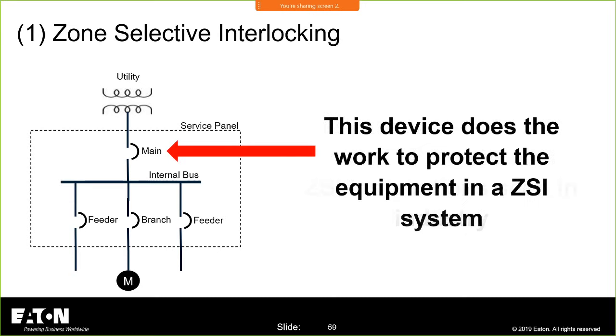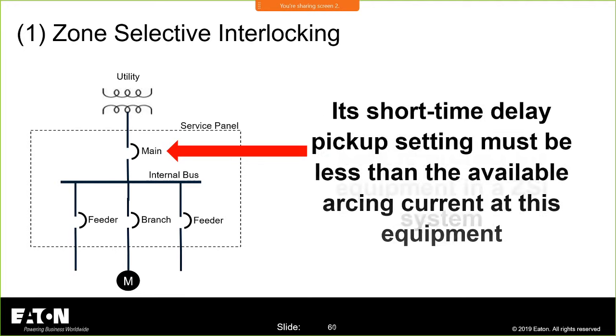because it doesn't get you selective coordination. In a ZSI system, that main device is what does the action to clear the fault. And it actuates on its short time delay pickup setting. So what you're going to have to do to meet this code is ensure the short time delay pickup setting is less than the arcing current. You're going to have to make sure that for the zone selective interlocking to work, that device's trip curve short time delay setting is to the left of where your arcing current is.